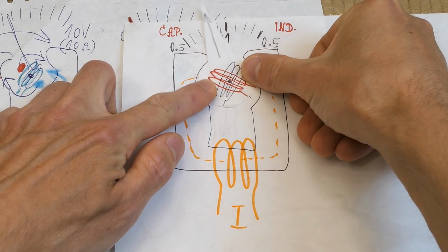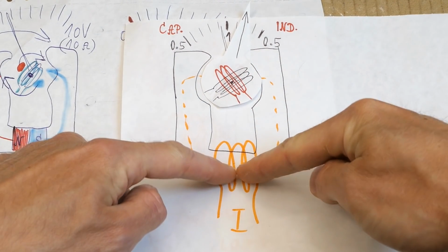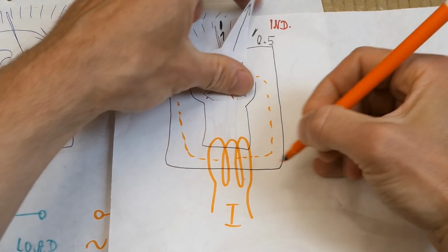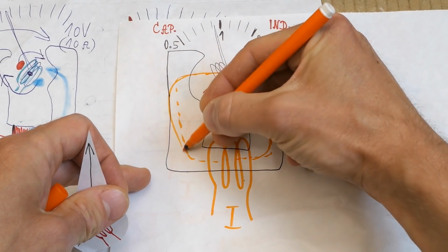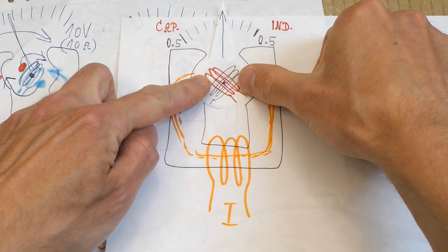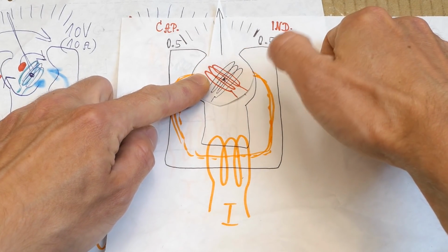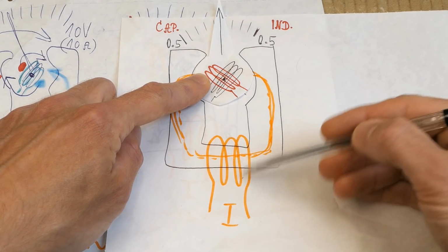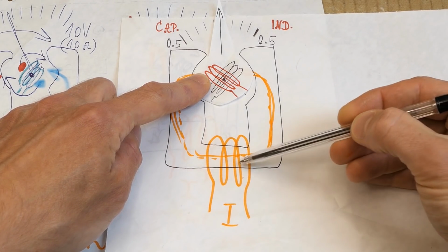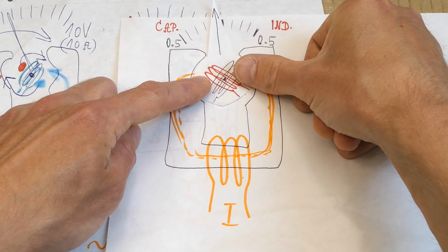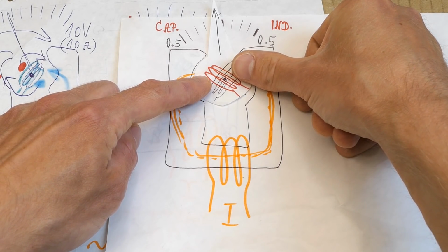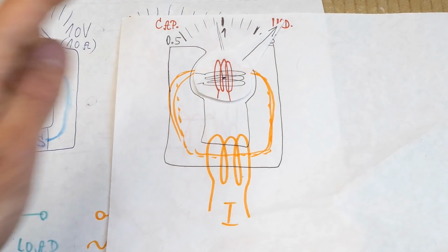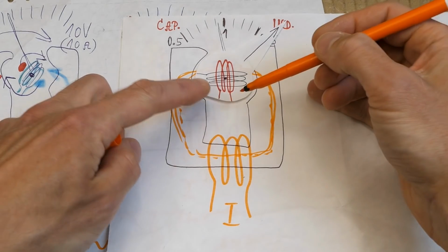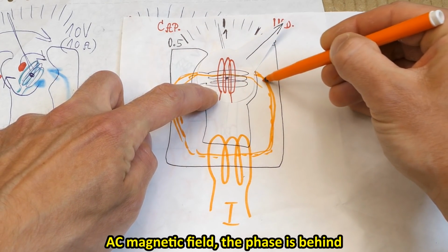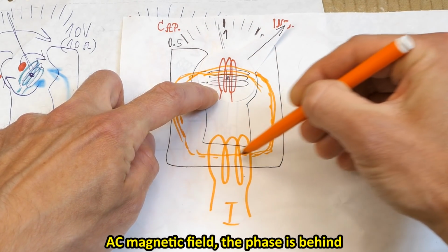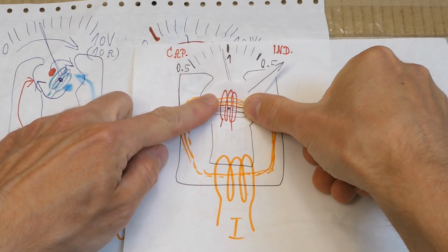And these two coils are basically turning in the magnetic field created by this current sensing coil. And this magnetic field is going through it this way. And in one of these coils the current is ahead, and in one of them the current is behind. Now if the load draws a current which is behind, this current sensing coil gets a current which is behind the voltage, and out of these two reference coils, the one where the current is behind will align with the magnetic field. Let's say the red one has the current behind the voltage and it aligns with this magnetic field which is also behind, and this of course indicates that it's an inductive load.